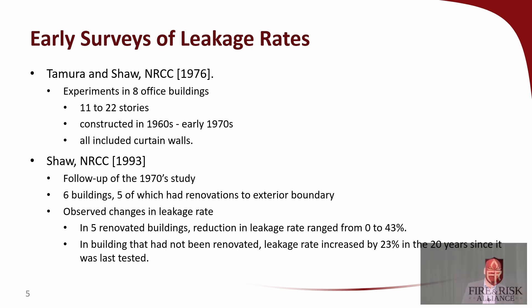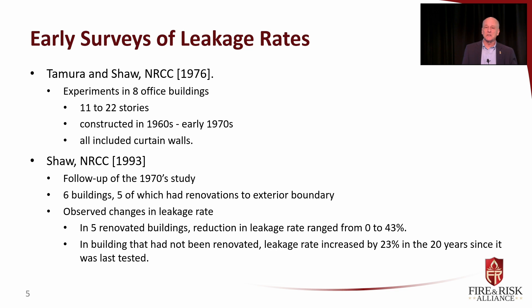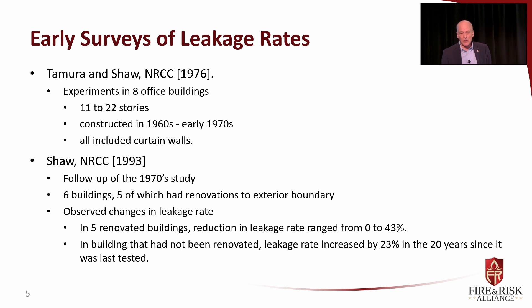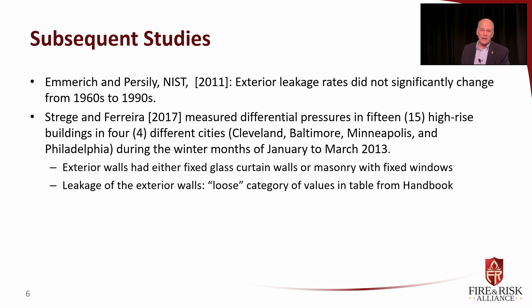Tamura and Shaw from NRC Canada in 1976 did experiments in eight office buildings constructed in the 1960s to early 1970s, all with curtain walls. Shaw from NRC repeated this study in 1993 with six buildings, five of which had renovations to the exterior boundary. In the renovated buildings, renovations in some cases did nothing to leakage and in other cases cut it by up to 43%. The building that had not been renovated saw leakage increase by 23% in the 20 years since it was last tested — that building got more leaky with age.